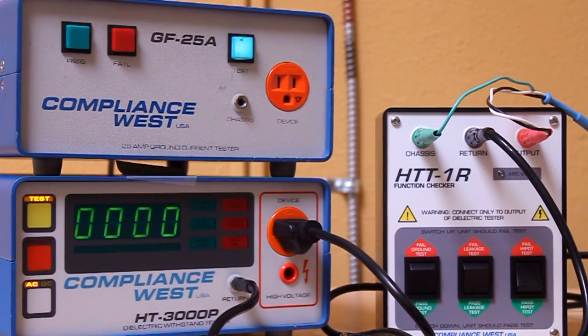The patented HTT-1R is provided with test leads which allow connection to any brand Hipot tester which uses a standard NEMA 15A receptacle and banana plug return leads to connect to the EUT and is made in the USA. The manual contains anticipated results and suggests testing procedures. The HTT-1R is provided with an ANSI Z540 calibration certificate.